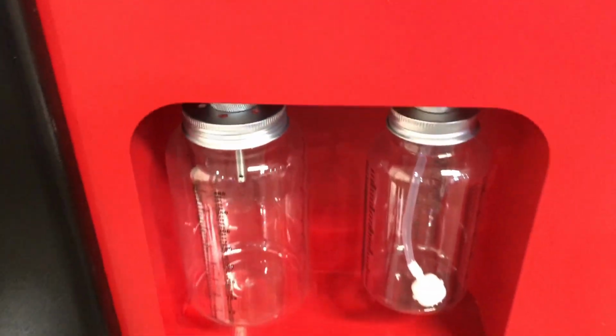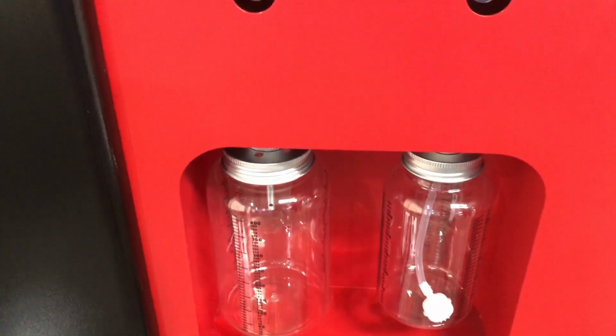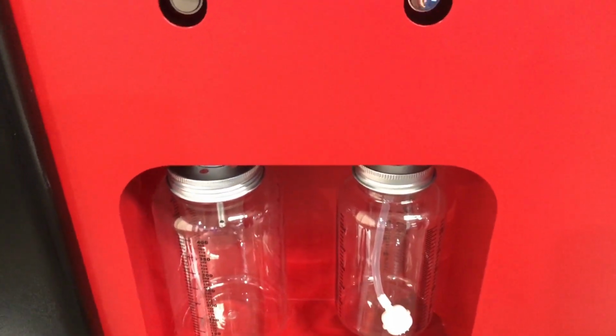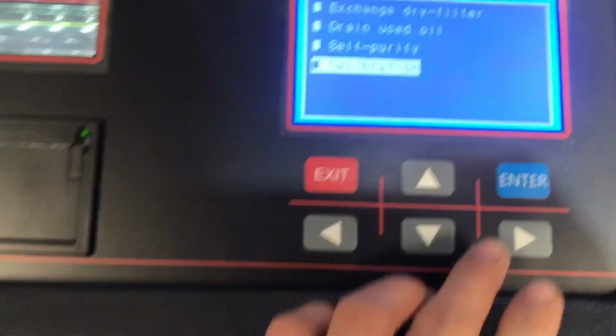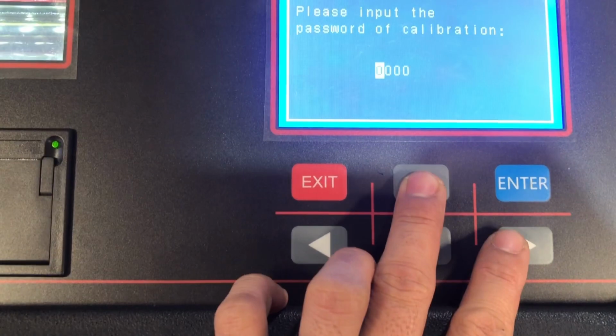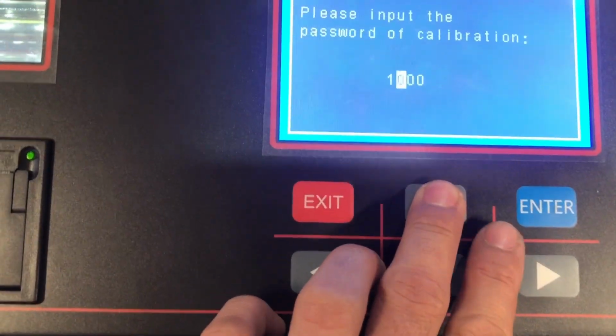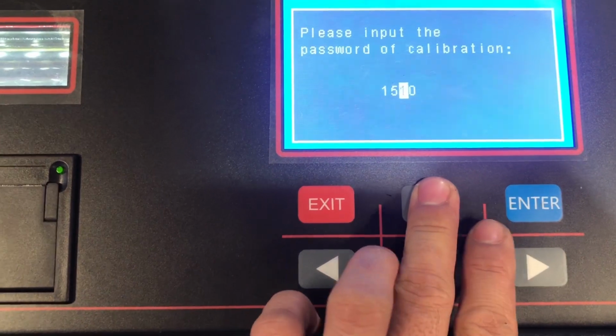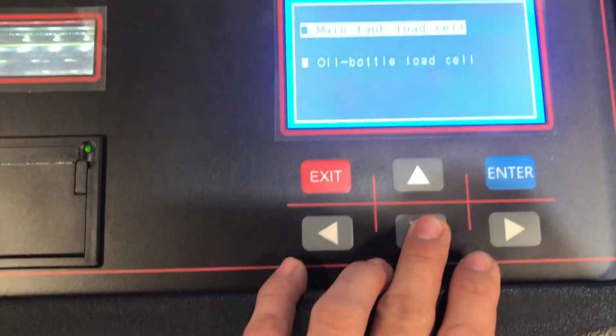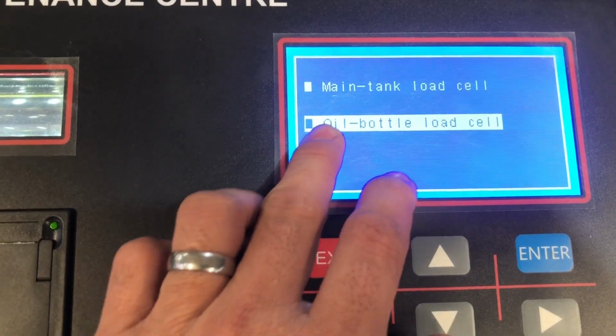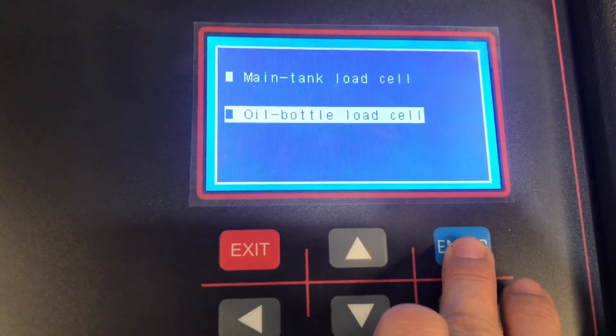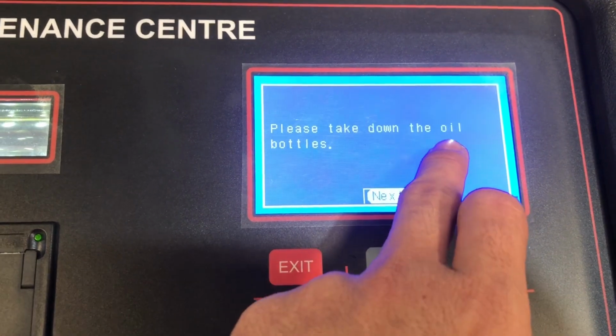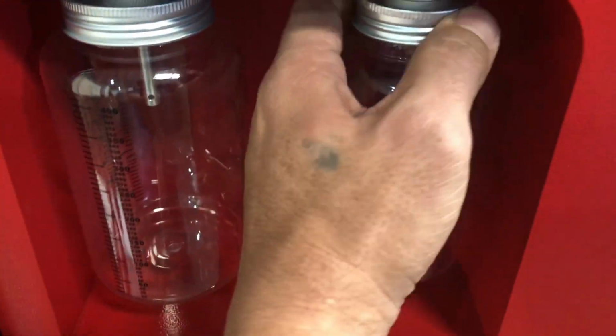You need to calibrate this oil tank, for the new oil and the used oil. Click calibration, set the password 15 10, enter, and then click this oil bottle load cell. Enter. Please take down the oil bottle. Take down, you need to remove this bottle.